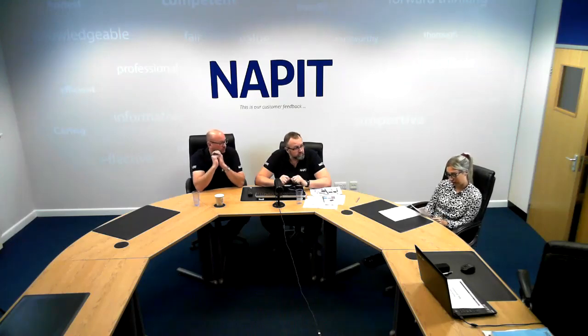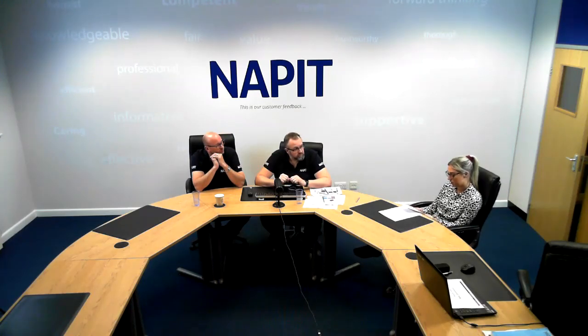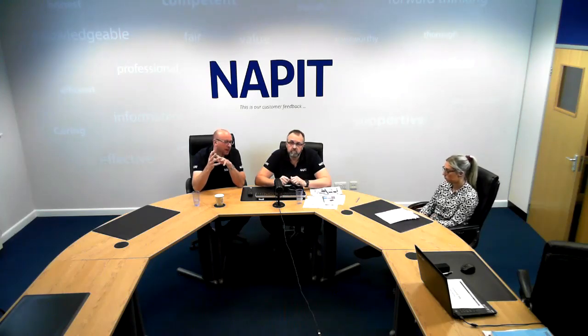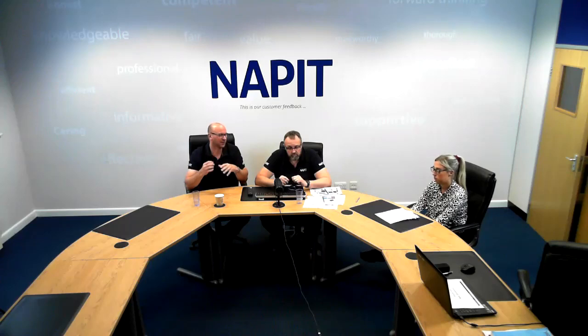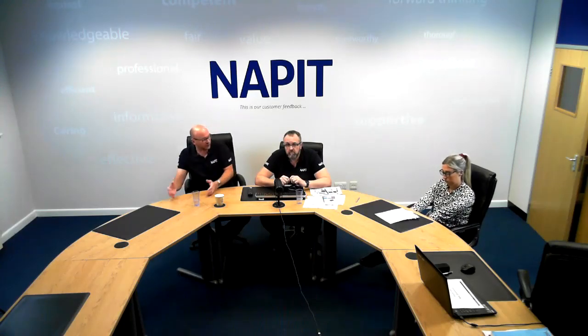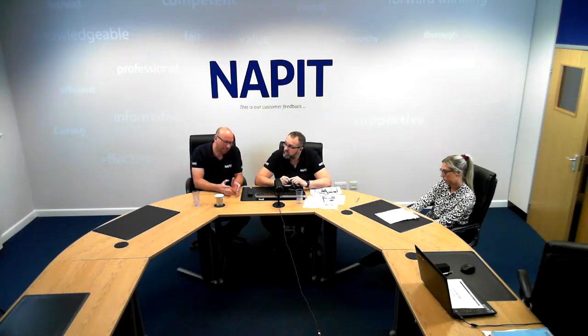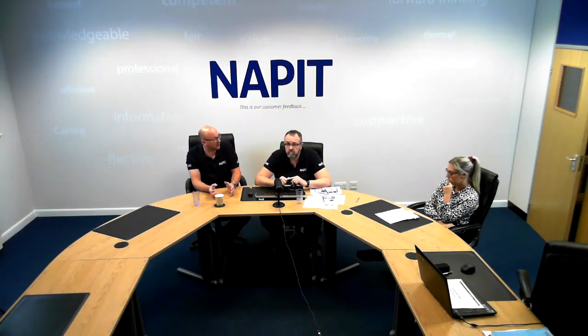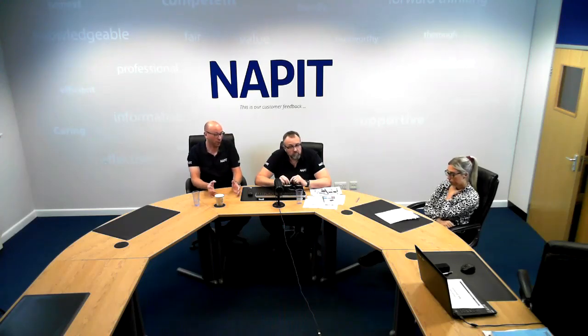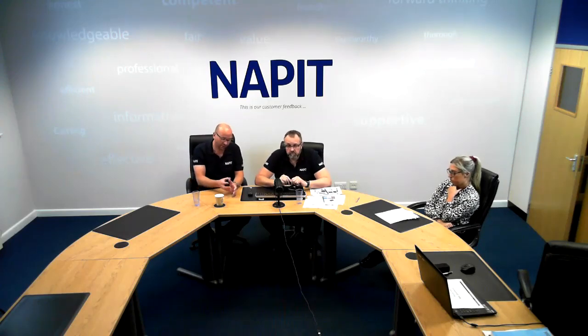The last question from one of our members was, what about submains in domestic properties - do these have to be RCD protected? Well, submains, it all depends on the cabling of where it's going and what type of submain it is. We can have submains from the mains position over to the consumer unit, and submains from a consumer unit outwards. With submains, if you can avoid using RCDs, you're so much better for it. You may not be able to avoid it if it's in a TT environment where you need an RCD for fault protection - then you may need an RCD to cover fault protection, but you'd be looking at a higher trigger value of maybe 100 or even 300 milliamp, and possibly a time delayed solution so you can cascade down through.